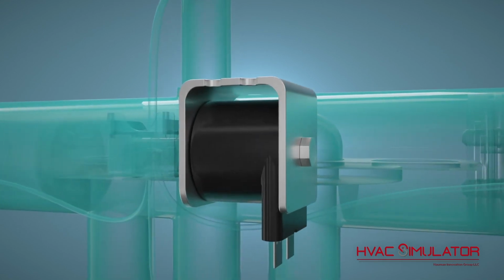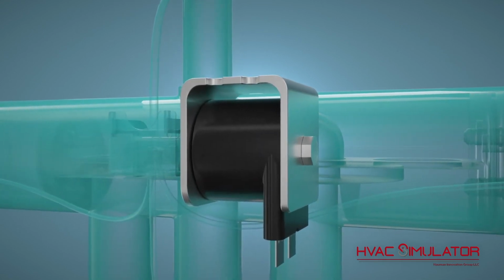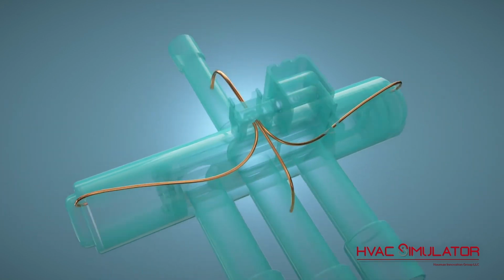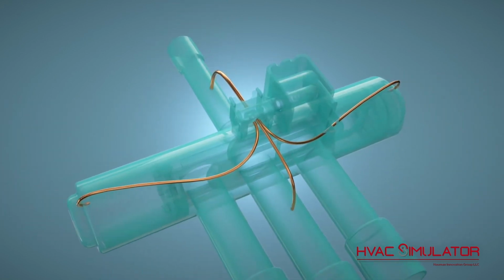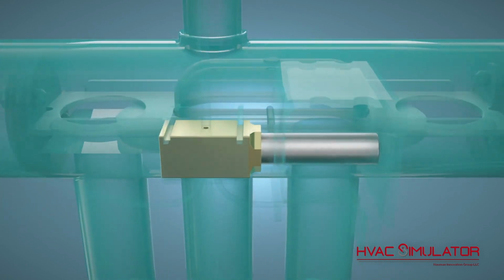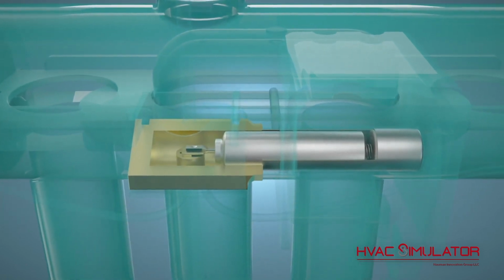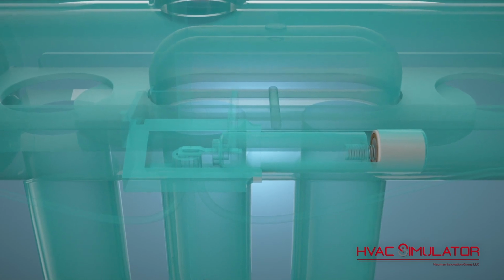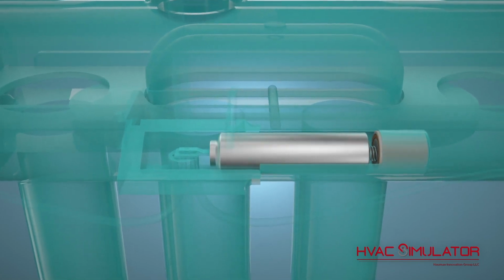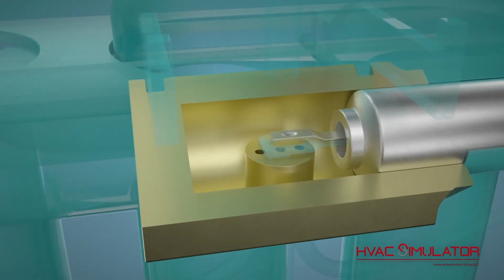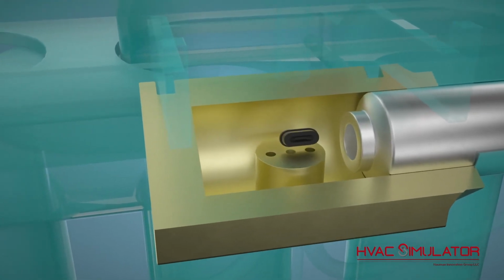The solenoid coil is an electromagnetic coil that receives electrical signals from the heat pump control system. The capillary tubes mimic the 4 pipes of the reversing valve. The pilot valve contains various components that respond to the heat pump's mode: the fixed core, the core spring, the core, the stem, which consists of a valve and gasket, and the valve seat.